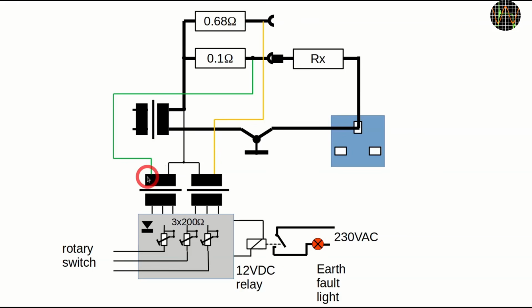On the PCB it connects to one of the transformers mounted on the PCB. The yellow wire from the soft earth return goes to the other transformer. It then gets complicated because the output of the 2 transformers are combined, rectified, and then drive a 12 volt relay, which in turn engages the earth fault light. Other contacts of this relay also disable the insulation test, which I did not show here.